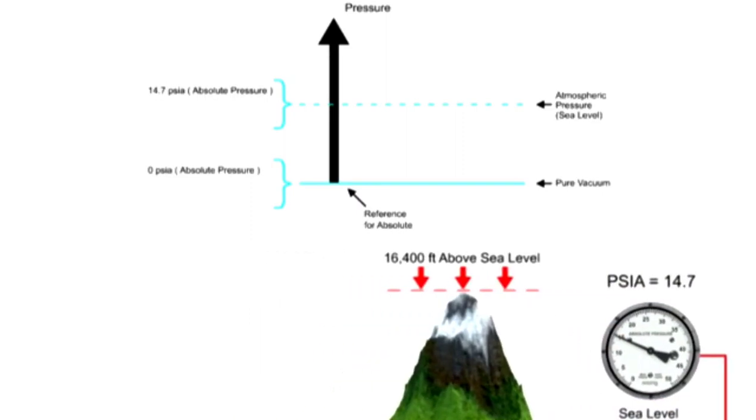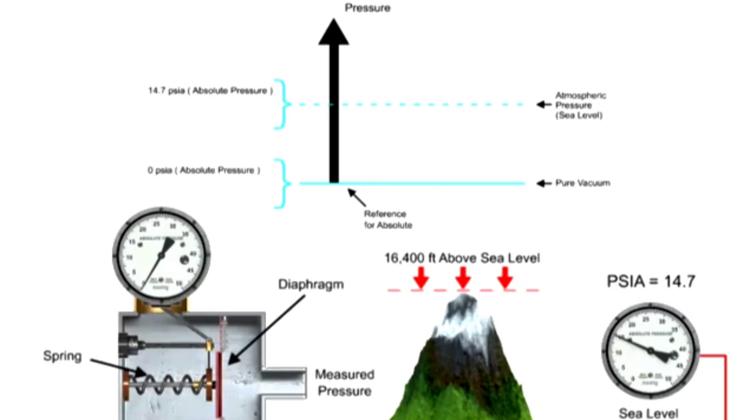A common method to measure absolute pressure is a mechanical diaphragm gauge. The diaphragm is a flexible membrane that flexes when exposed to pressure. On the opposing side of the diaphragm is the reference pressure, which is vacuum for absolute pressure.